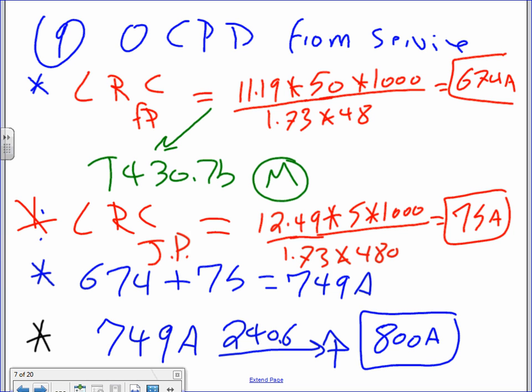So that's the difference between a fire pump and any other motor. On a fire pump, they size the overcurrent protection device based on the locked rotor current. Unlike other pumps, where they size it based on the full load current times 2.5, from the service side they size it based on the locked rotor current. Meaning, guys, because it's so important, they want that fire pump to keep working until it burns itself out in the process of protecting your building from the fire, which makes sense, right? They want the fire pump to hold the ground until the firefighters pull in and take care of business, basically, and support the firefighters in fighting that fire.